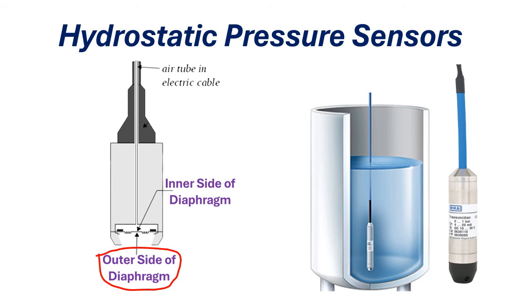This transmitter has a pressure diaphragm. The outer side of this diaphragm is in contact with liquid, while the inner side is vented to atmospheric pressure. The pressure is proportional to the height of the liquid above the sensor. Hydrostatic pressure transmitters are used in industrial plants, reservoirs, and open channels.